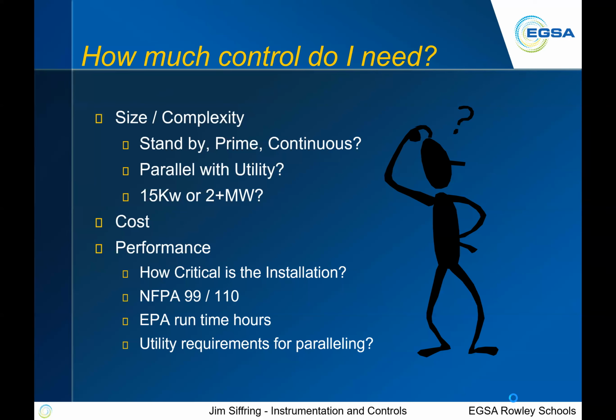What's our cost? Obviously, there's a cost requirement for everything. What's our budget? What's our performance? How critical is the installation? Is it a hospital? Is it a data center, or is it just keeping the lights on in the house? NFPA 99 or 110 requirements. What's our runtime hours that EPA is going to let us run? If we're going to parallel with utility, are there any requirements that the utility is going to have on us? Are we going to have some sort of relaying and things such as that?